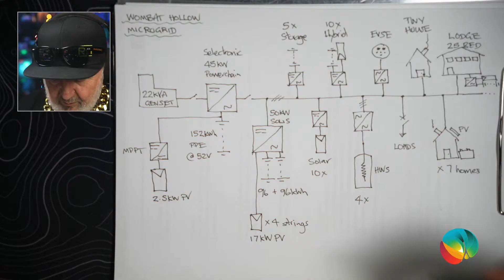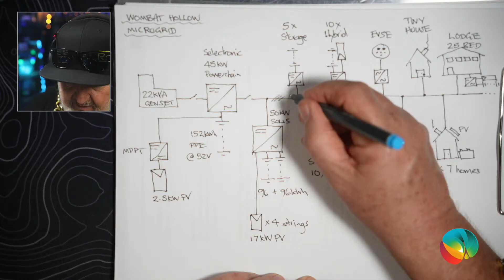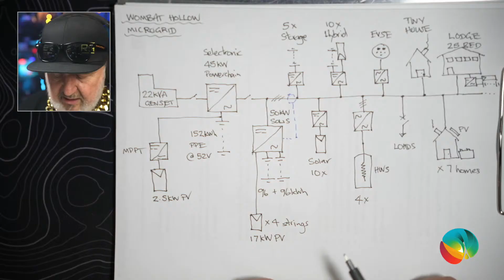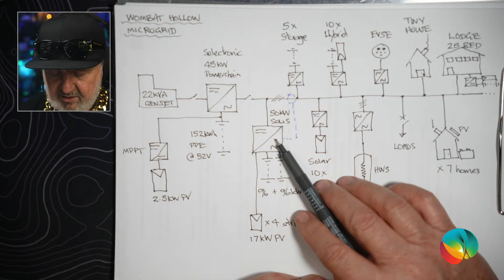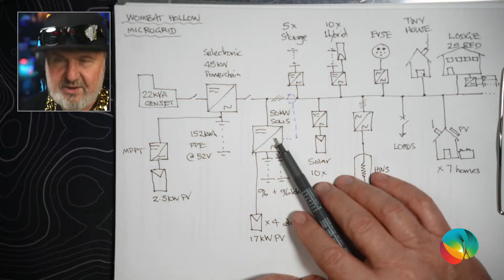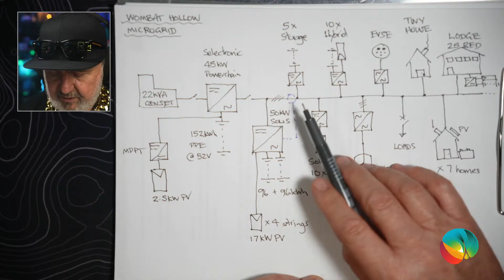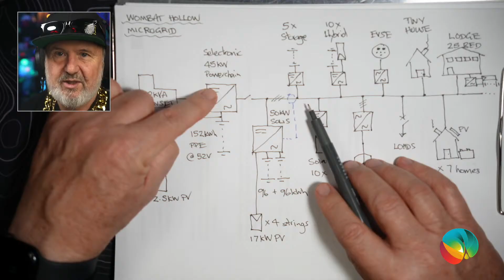So what's happening is there is a CT that connects and communicates, or it's a CT and a meter, so it's doing full real power, active power calculations, and that CT is telling the Solis inverter how much load there is on the microgrid. And so the Solis inverter, because it's AC coupled, is working in parallel with the grid forming system. This inverter will try to support the loads as closely as possible. So if all of the loads on this network are 8 kilowatts, it will output 8 kilowatts, which means that the grid forming system is basically doing nothing. It's sitting there just creating a stable grid and not even discharging its batteries.